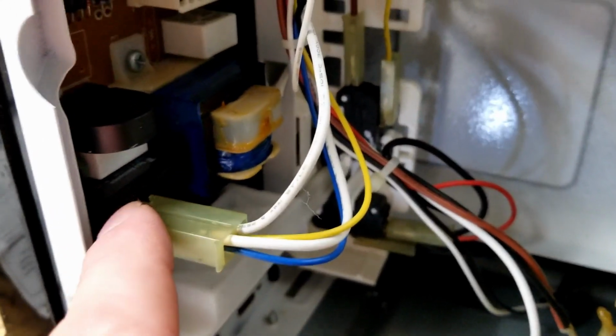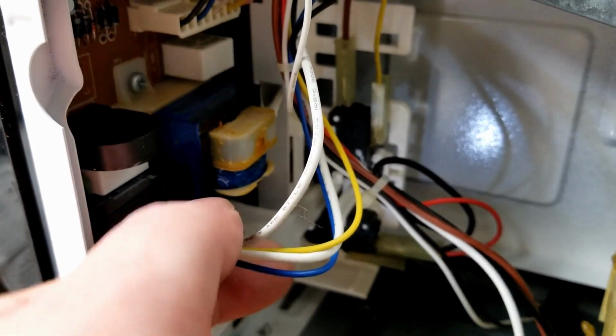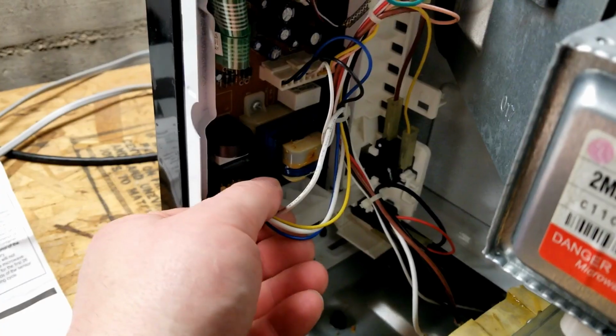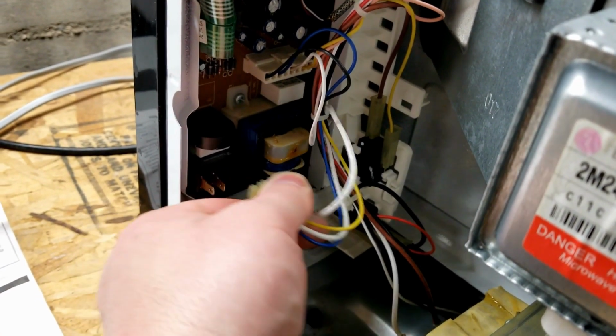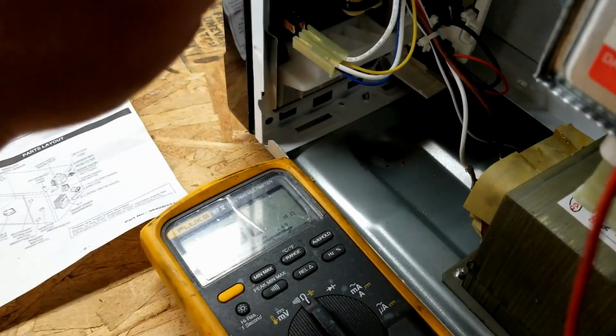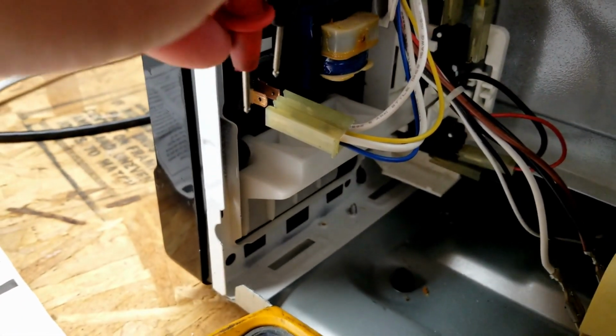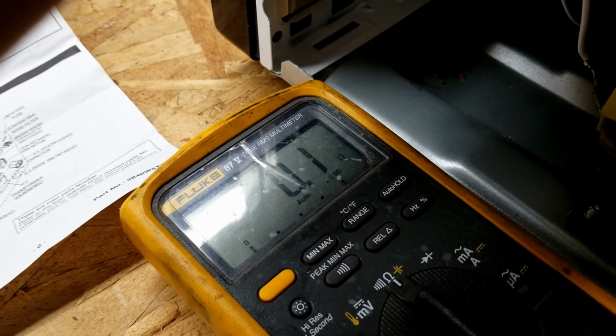So we're suspecting that this is shorted, or in essence this relay is just stuck closed. If we were to disconnect this and put our meter to ohms and then just touch across there, sure enough that relay is closed right now.